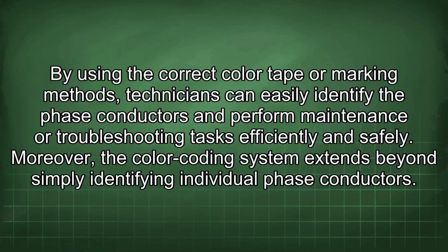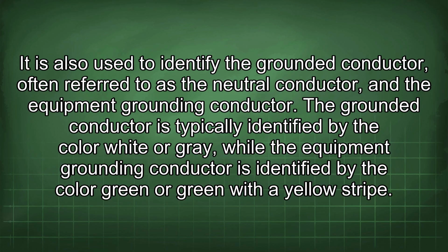Moreover, the color coding system extends beyond simply identifying individual phase conductors. It is also used to identify the grounded conductor, often referred to as the neutral conductor, and the equipment grounding conductor. The grounded conductor is typically identified by the color white or gray, while the equipment grounding conductor is identified by the color green or green with a yellow stripe.